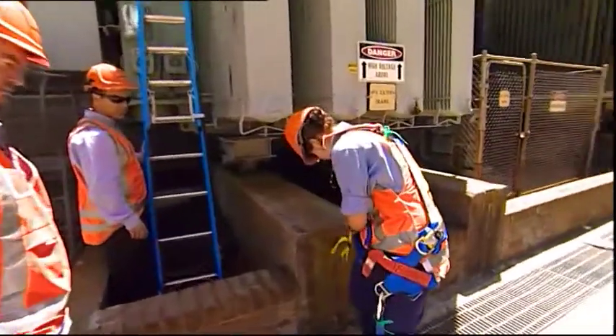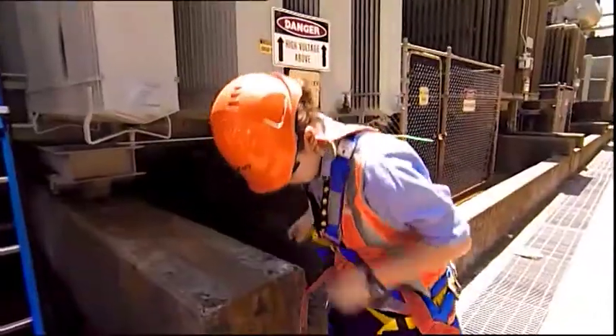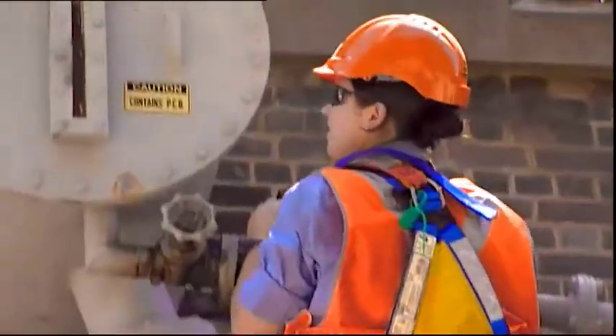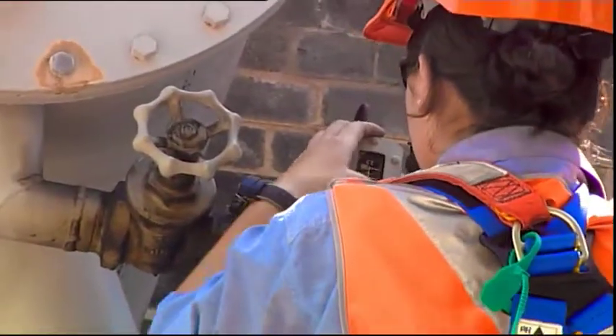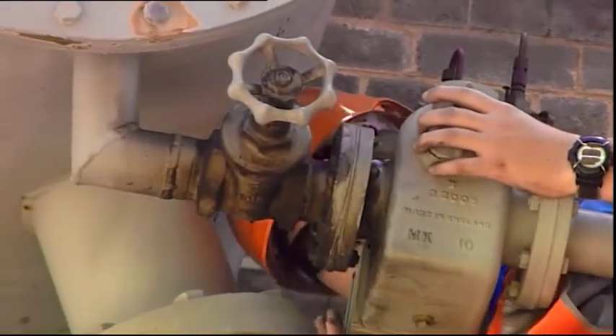412. Got into the harness and climbed up onto the transformer to check the Buchholz relay. It's just a relay that senses the oil, and we have to make sure that's all okay and there's enough oil in there and nothing leaking out of it. So just a quick check over of that.